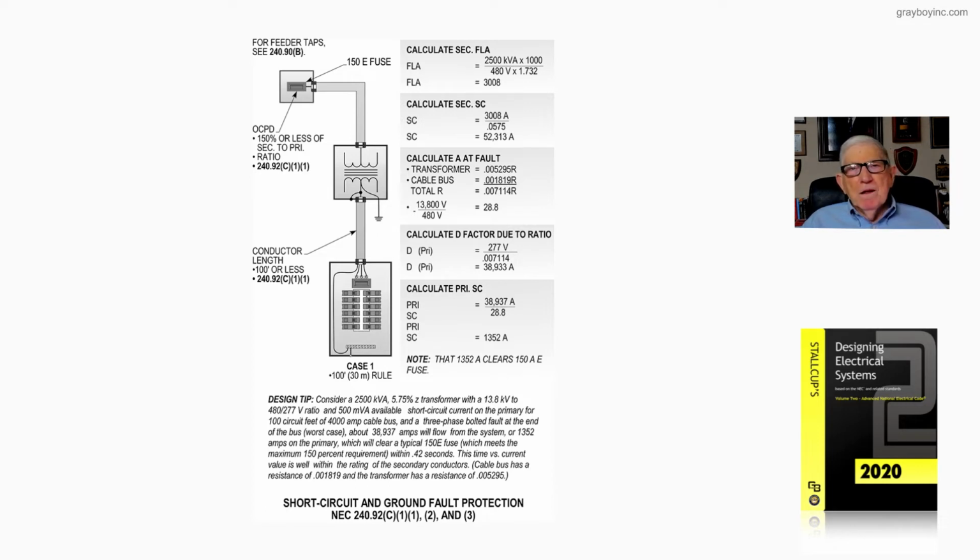But now remember, we're looking at conductor taps over 25 foot up to 100 foot now, based upon transformer secondary conductors. And we're in supervised industrial locations. Usually that means you have supervision to ensure we have qualified people that will service this installation you see in the figure. And usually they have an engineering staff aboard. You want to be qualified to do this, and most times engineers would do this.